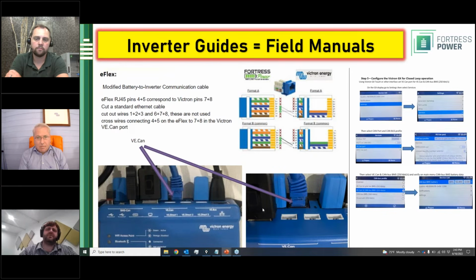One of the most important things to know about Victron communication is that what comes out of the eFlex or eVault Max isn't just one communication circuit. We have a separate communication circuit for the batteries, another for one type of inverter using Modbus communication, and a different one for CAN bus communication for other kinds of inverters. The pins on the communication output don't always match up with what the inverter needs. On some inverters, getting this communication correct is very important so you don't short out the communication board. Other inverters are more robust, but you can find the map of that for Victron.